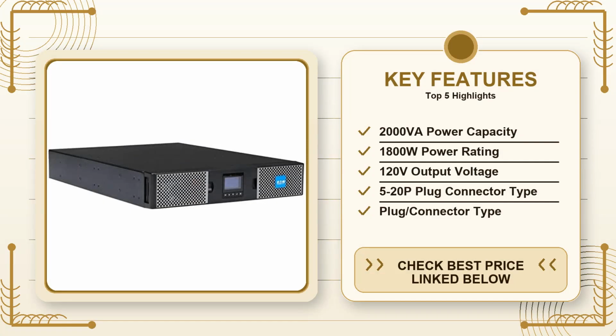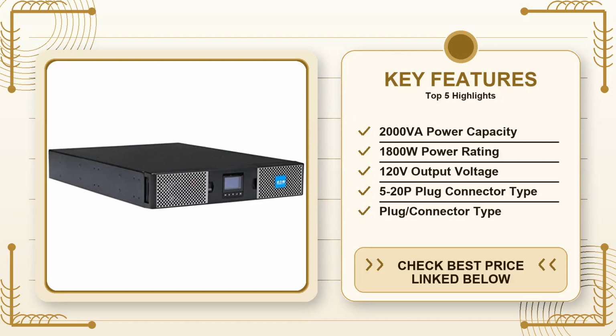However, if you try to push the UPS close to its 1800W limit, say you're powering a server rack with several drives and a heavy-duty workstation, the runtime drops dramatically to under 5 minutes. That's a trade-off you have to accept: the higher the load, the shorter the cushion.